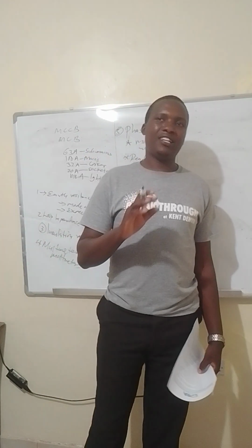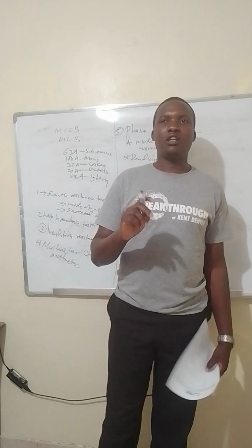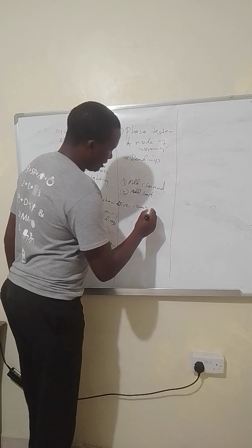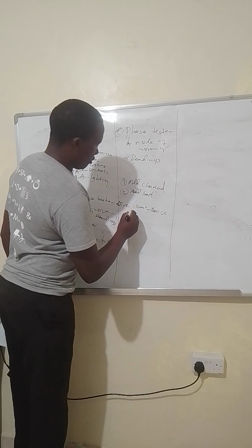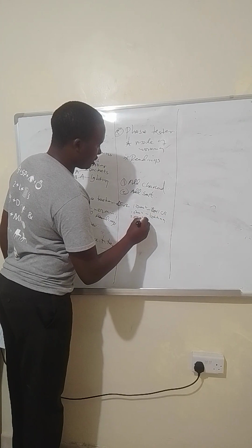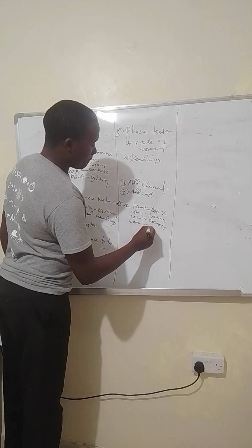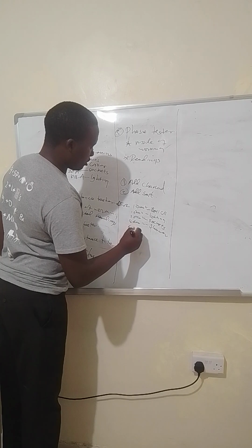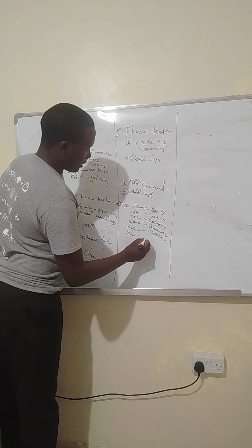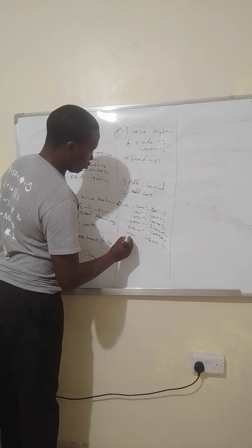Cable selection: 1.0 millimeter square is used in bell circuits. 1.5 millimeter square is used in lighting. 2.5 millimeter square is used in sockets. 4.0 millimeter square is used in showers. 6.0 millimeter square is used in cookers. 10.0 millimeter square is used like sub mains. And 20 to 25 millimeter square is used as mains.